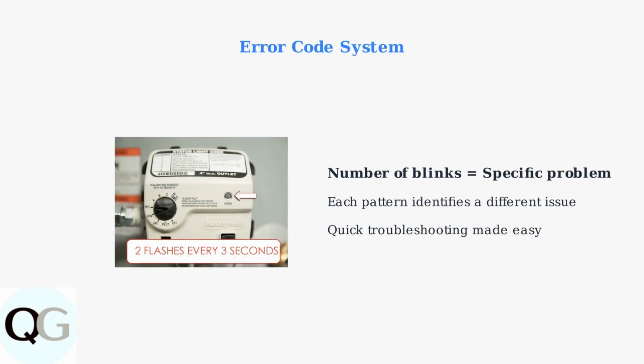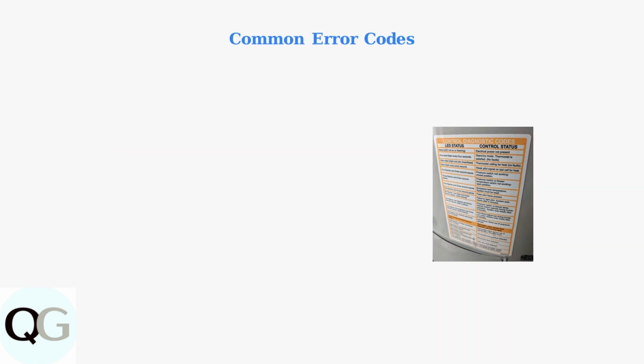The error code system is simple. The number of blinks corresponds to a specific problem. This allows for quick and accurate troubleshooting of your water heater. Here are the most common error codes you'll encounter with your Honeywell water heater. Each code indicates a specific issue that needs attention.